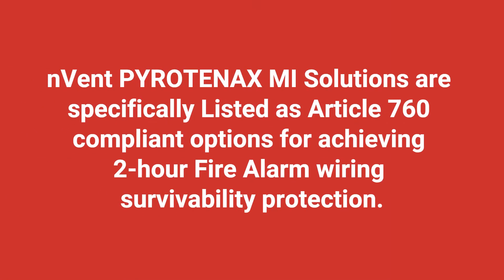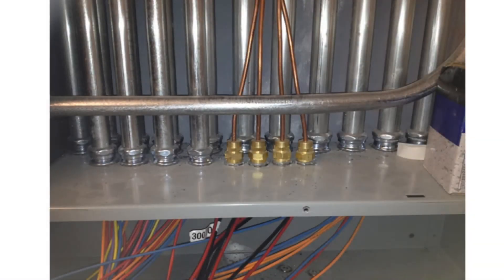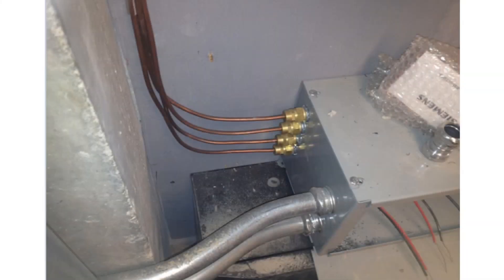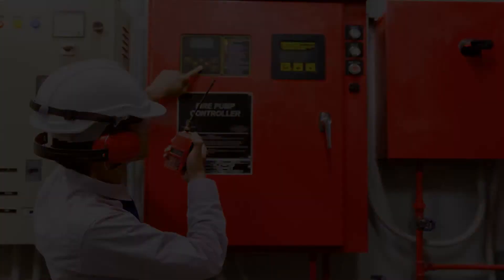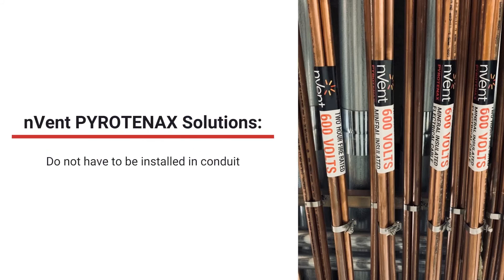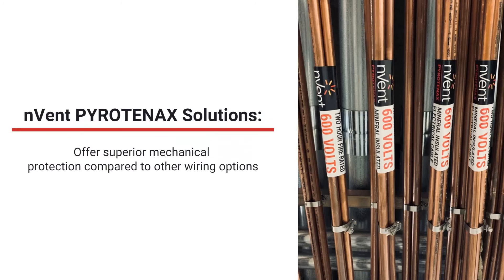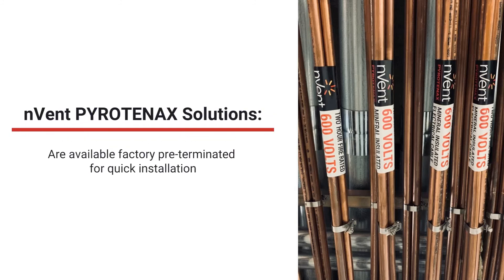Pyrotenax MI solutions are specifically listed as Article 760 compliant options for achieving two-hour fire alarm wiring survivability protection. Many people in the industry know that Pyrotenax MI cables come in many sizes and configurations of power cable. In addition, they are also available in twisted pair shielded and non-shielded cables specifically engineered for fire alarm systems. Pyrotenax MI solutions have no vertical limitations, do not have to be installed in conduit, offer superior mechanical protection, have approved splice options, require fewer supports, and are available factory pre-terminated for quick installation.